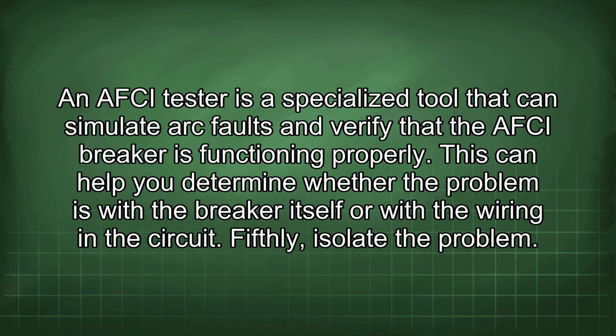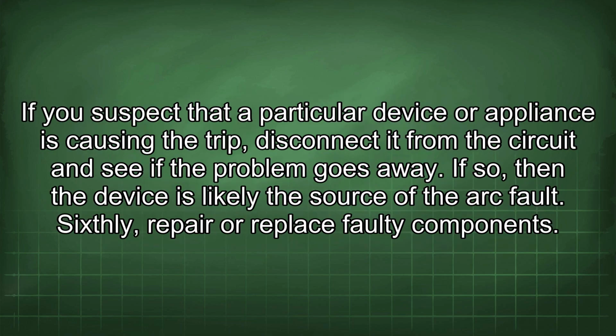An AFCI tester is a specialized tool that can simulate arc faults and verify that the AFCI breaker is functioning properly. This can help you determine whether the problem is with the breaker itself or with the wiring in the circuit. Fifthly, isolate the problem. If you suspect that a particular device or appliance is causing the trip, disconnect it from the circuit and see if the problem goes away. If so, then the device is likely the source of the arc fault.